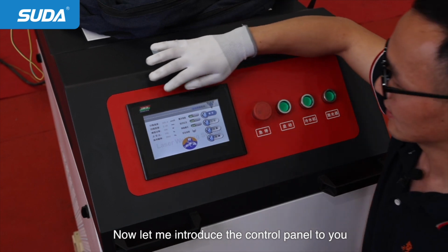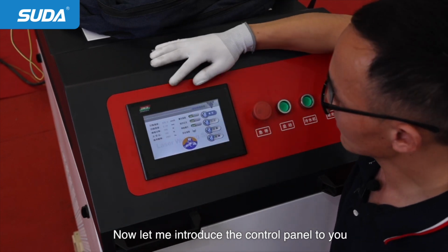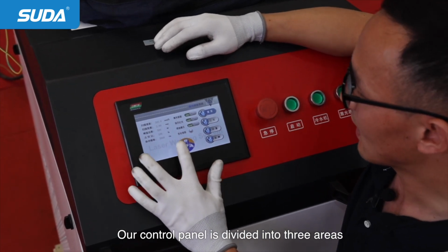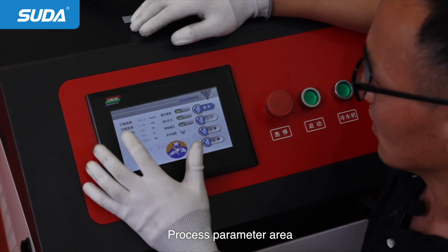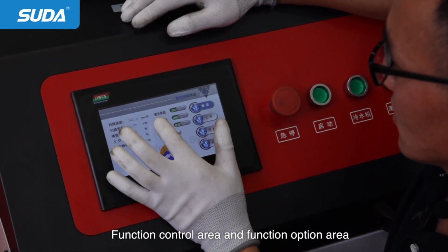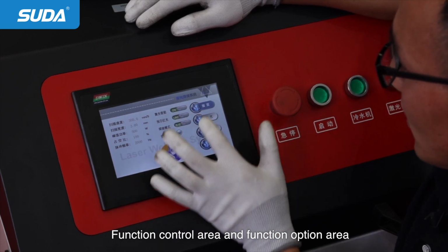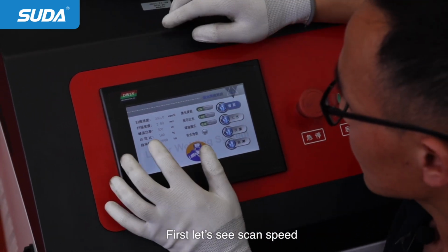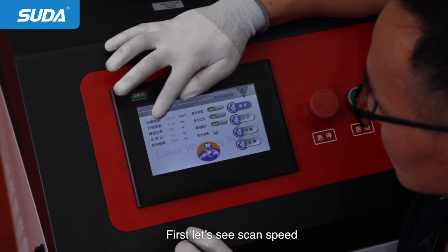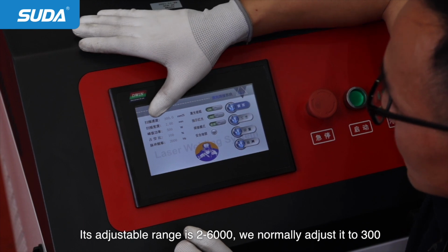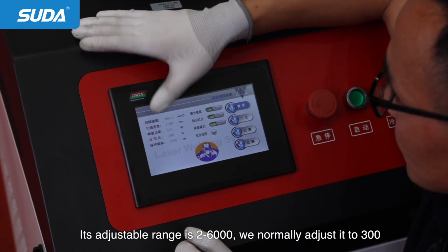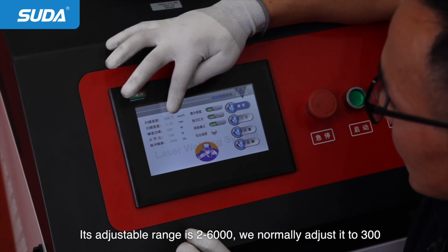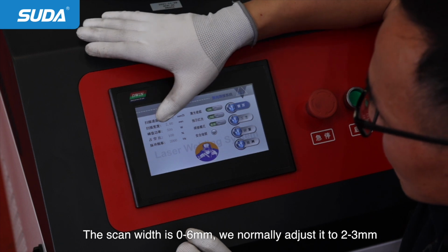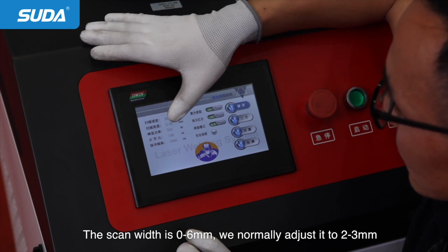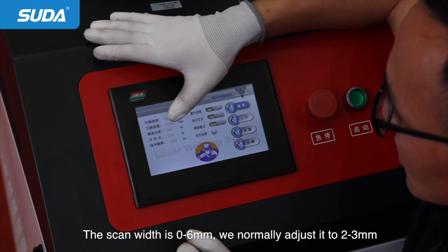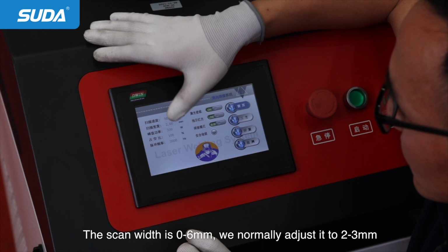Now, let me introduce the control panels. Our control panel is divided into 3 areas: process parameter area, function control area, and the function option area. First, let's see scan speed. Its adjustable range is 2 to 6,000. We normally adjust it to 300. The scan width is 0 to 6 millimeters. We normally adjust it to 2 to 3 millimeters.